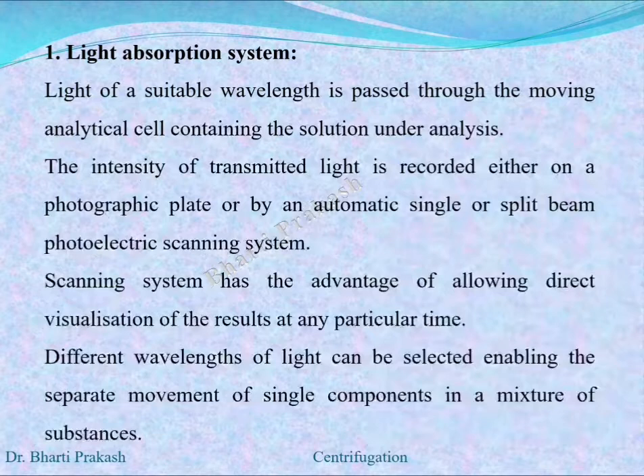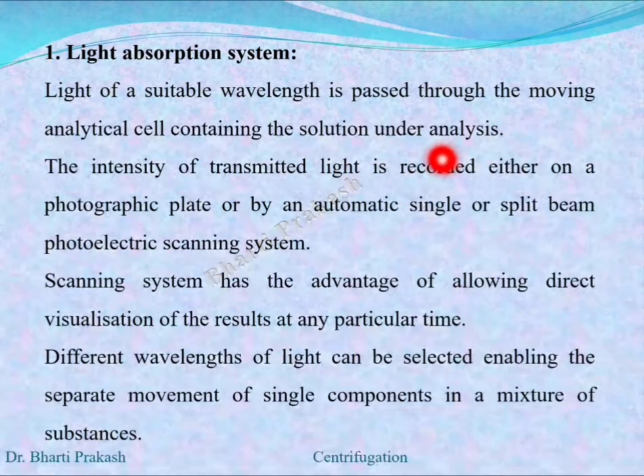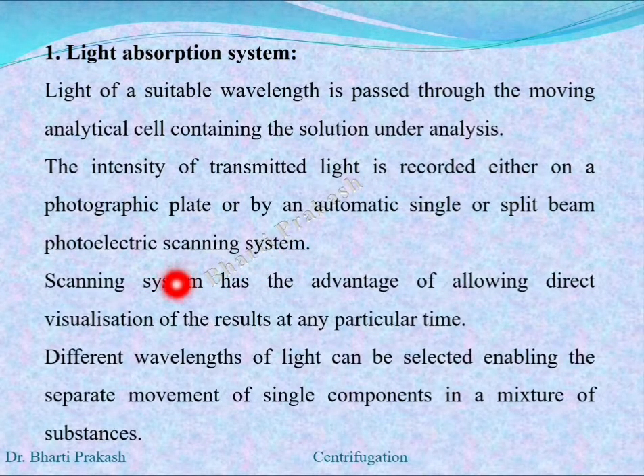In the light absorption system, light of a suitable wavelength is passed through the moving analytical cell containing the solution under analysis. The intensity of the transmitted light is recorded either on a photographic plate or by an automatic single or split beam photoelectric scanning system. The scanning system has the advantage of allowing direct visualization of the results at any particular time. Different wavelengths of light can be selected, enabling the separate monitoring of a single component in a mixture of substances.